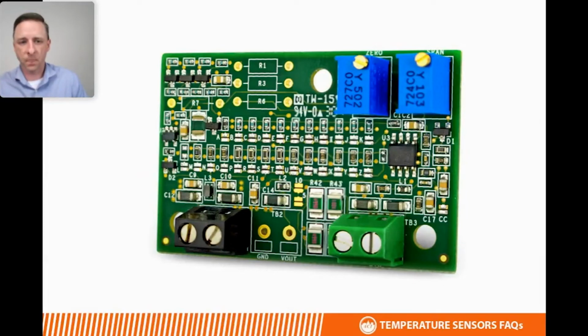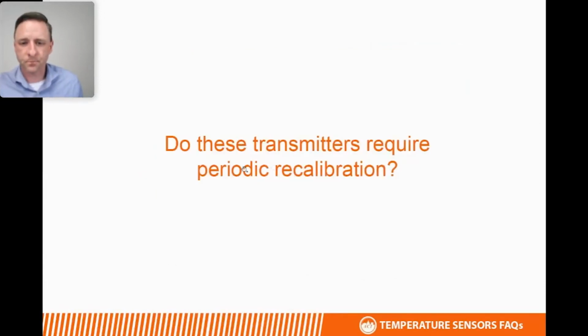The standard TTs do not come with an NIST certificate, and the sensor and the transmitter may not be built together. They might be paired together and then calibrated to the specific temperature span that's required.